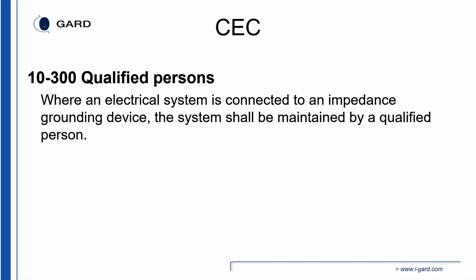When you have phase to phase, you're going to get 600 volts A to B, B to C, C to A. When you measure phase to ground, you're going to get 600 volts on the two unfaulted phases and 0 volts on the third phase, or the faulted phase. So a qualified person should be able to recognize that that is a ground fault and not necessarily a blown fuse. If you had a blown fuse, you would probably have something like 347 volts to ground on the two of the phases and 0 volts to ground on the blown fuse phase. So I guess you have to make that determination, and a qualified person should be able to do that.